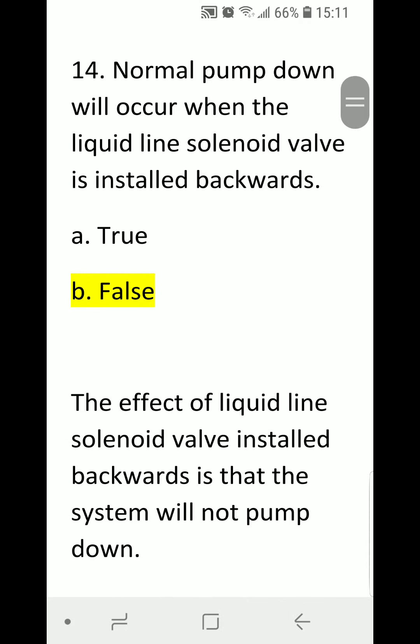Number fourteen: normal pump down will occur when the liquid line solenoid valve is installed backwards or reversed. A) true, B) false. Correct answer is B, false. The effect of a liquid line solenoid valve installed backwards or reversed is that the system will not pump down.